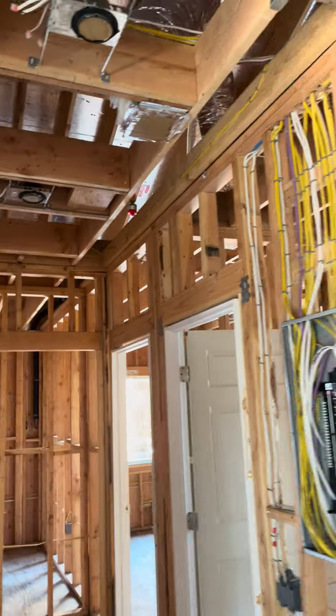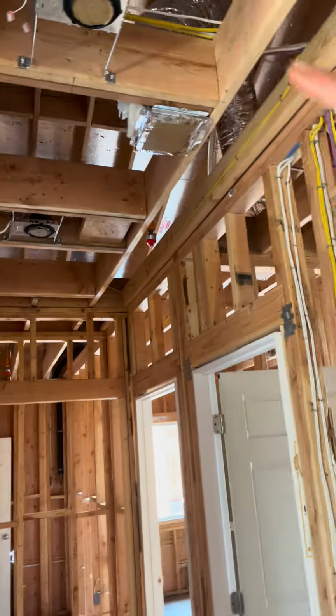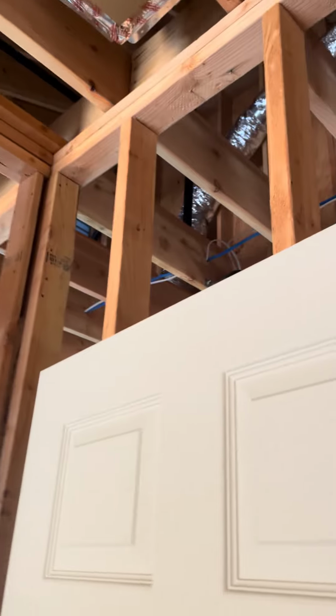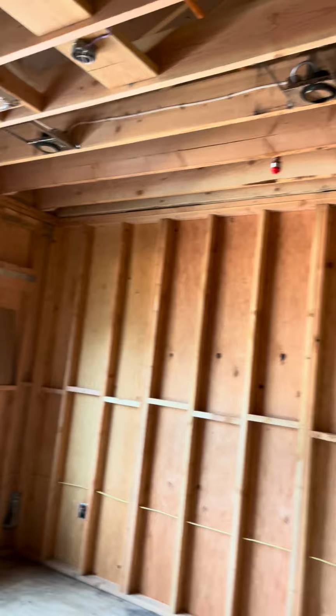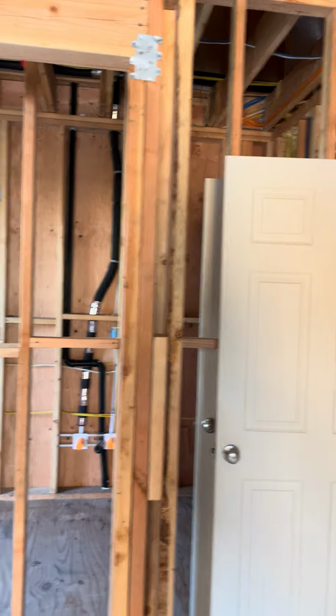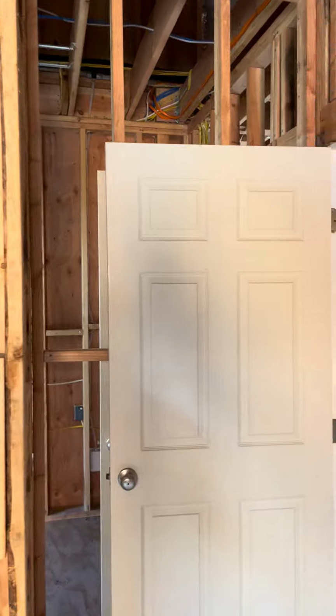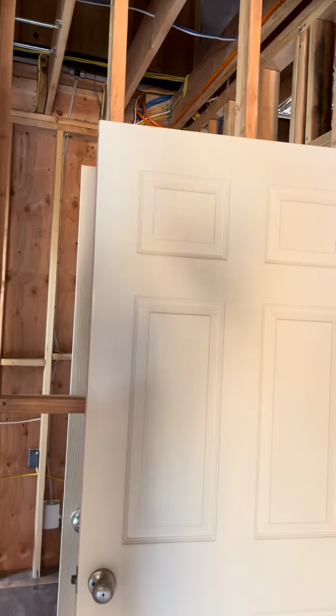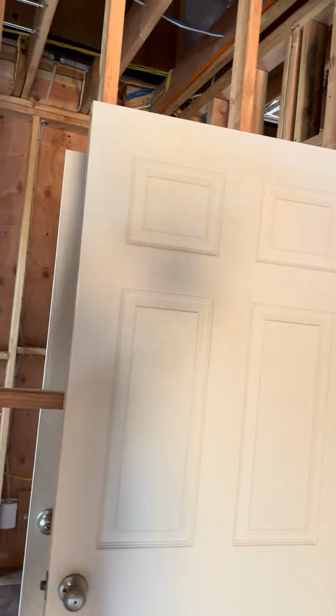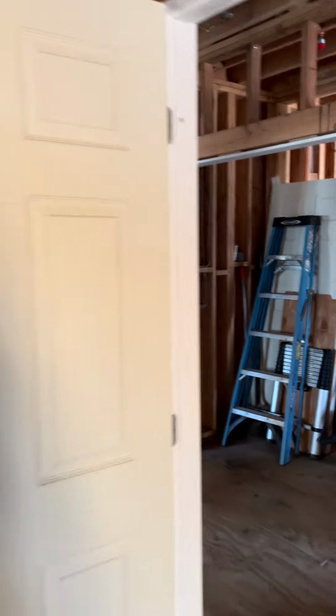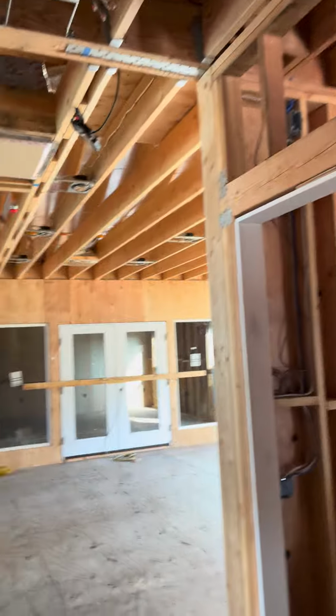Over here we have a couple of bypass ducts. What I mean by bypass duct, you see here the duct goes up and over and it comes into the room, but it's not hooked to the unit. Basically the theory is the room will get pressurized with this, and to relieve the pressure and to afford a better mixing of the air throughout the house, we're going to relieve a little bit of that by allowing the air that's being pushed into the room to get pushed up into this and empty into the hallway here close to the return.